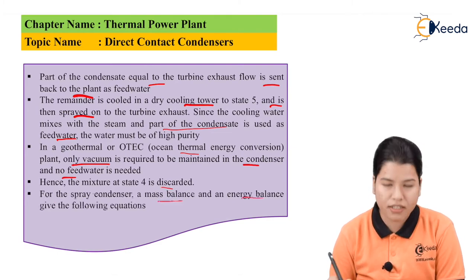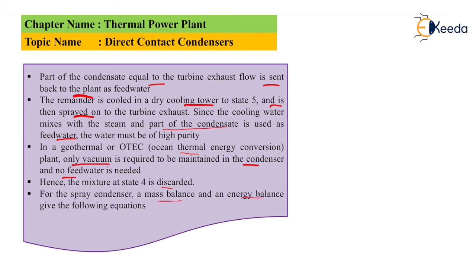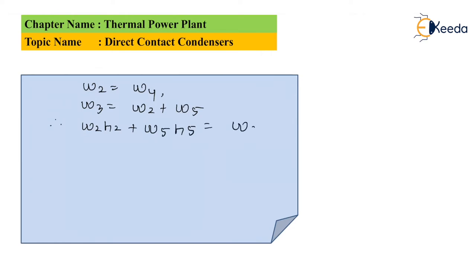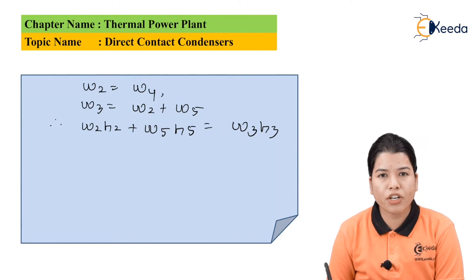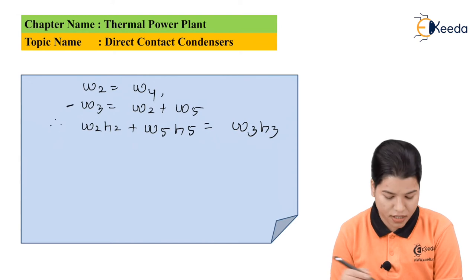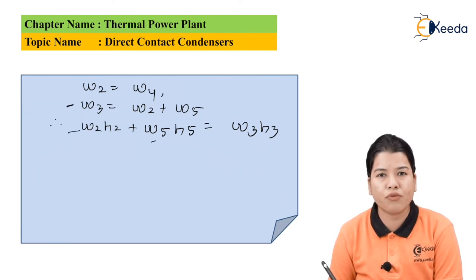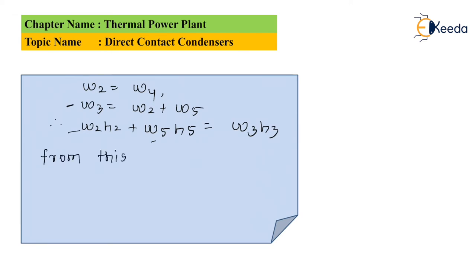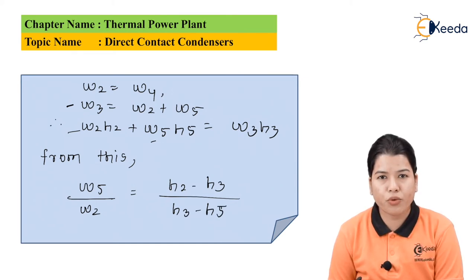For spray type condensers, a mass balance and energy balance can be given by the following equations. w2 is equal to w4; similarly, w3 is equal to w2 plus w5. Hence, w2·h2 plus w5·h5 is equal to w3·h3. From this equation we can write: w5 divided by w2 is equal to (h2 minus h3) divided by (h3 minus h5) — this is equation number one.